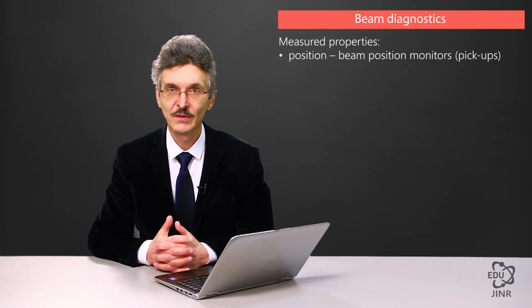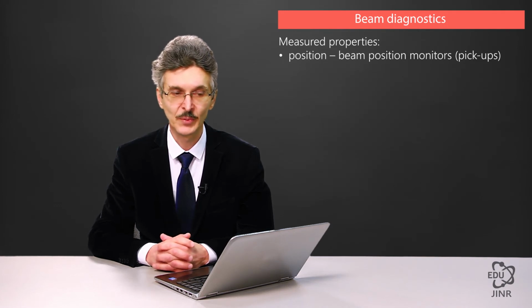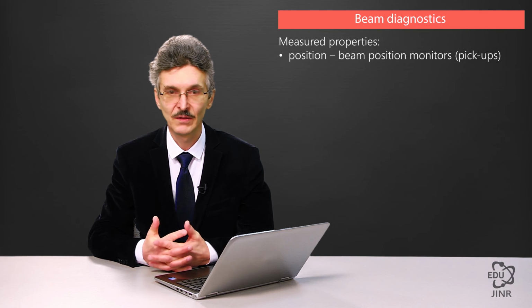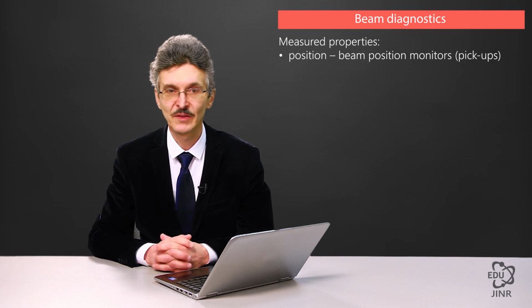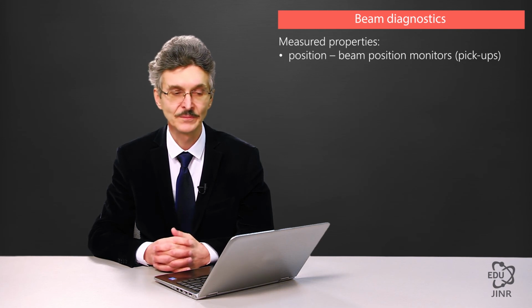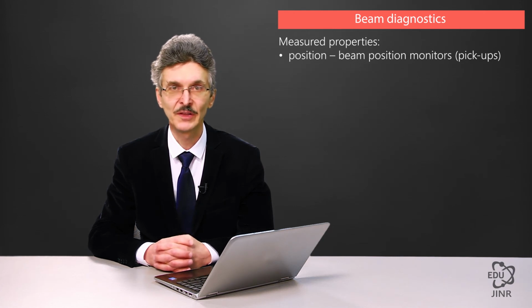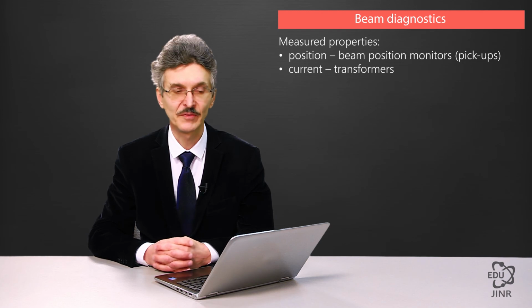Here, diagnostics comes into play. Diagnostics includes a lot of multifaceted devices. Operational characteristics of each instrument depend on what kind of parameters of the beam it measures. There are special beam position monitors. They are usually called pickup stations because of their design. They measure the center of gravity position of a particle bunch circulating in the accelerator. There are sensors that measure the current. As a rule, these are current transformers.